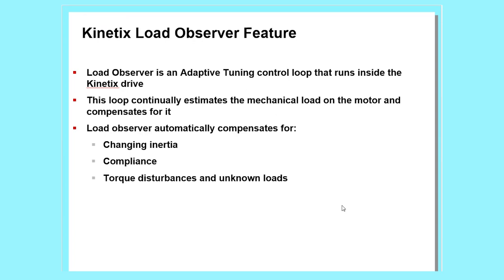Now we'll talk about load observer. Load observer is an adaptive tuning control loop that runs inside the Kinetix drive. This loop continually estimates the mechanical load on the motor and compensates for it. Load observer automatically compensates for changing inertia, compliance, and torque disturbances.